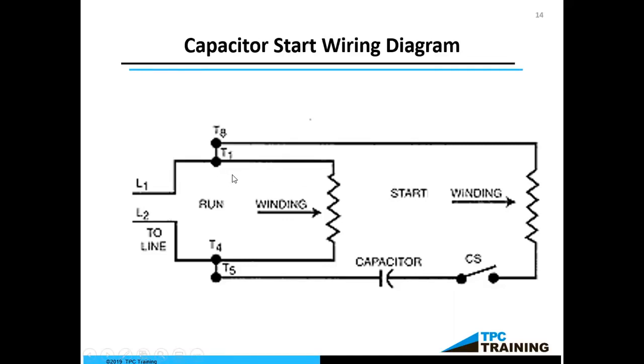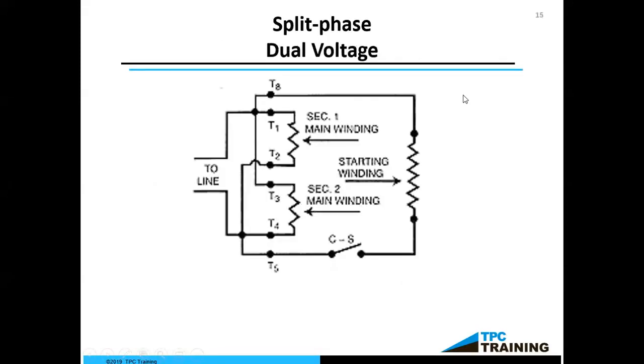And then one of the last things that I want to mention on this particular diagram is that if we were ever going to reverse a single-phase motor, we have to actually bring out T8 and T5. And so a drum switch works very well with that. You can really reverse that really well, bring those leads out. You can have forward, reverse, or you could even have off in the middle position. So on a single-phase motor, know that T8 and T5, that's what we have to actually reverse.